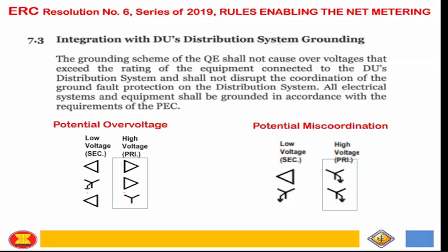And then for the grounding system, yung mention ko for ungrounded primary, no, there's a potential on over voltage and then potential miscoordination for the distribution side, no. But ang problem nito, medyo mahirap i-deal with the grounded system at the primary because every now and then parang magiging dynamic yung scheme ng distribution system. Imagine if every now and then we don't know, no, kailangan mag-maintenance yung DG, then iiba na naman yung fault current, no? Then mag-change tayo ng mga scheme, ng settings na i-coordinate natin with the DG. So ina-encourage yung ungrounded na system to contribute yung to avoid the redistribution of fault current.